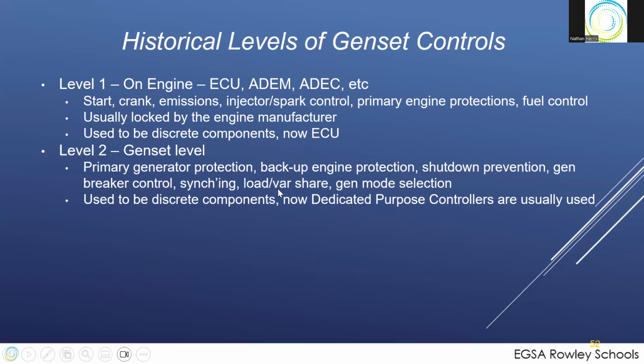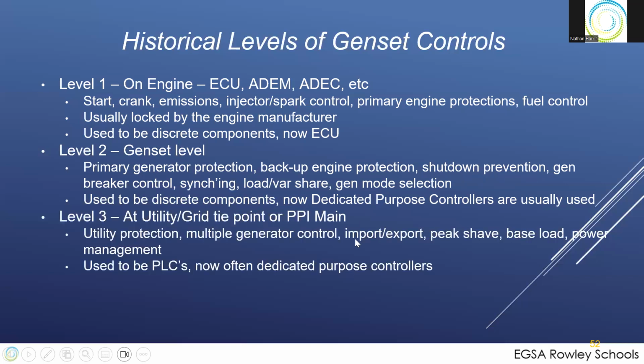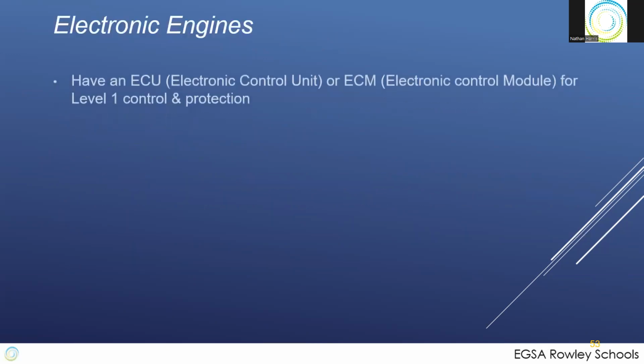Generator breaker control, synchronizing, load and VAR share, gen mode selection is done at the second level. Again, used to be discrete components. Now dedicated purpose controllers are often used for this. And level 3 was at the grid utility tie point. So this was synchronizing with the utility, import-export mode, peak shave, peak lopping, IRC control, power management things that go on with multiple gensets. It has to have some kind of a master controller, and that's the level 3 control. So that was historically the 3 levels we had: on the engine, on the genset, at the tie point.